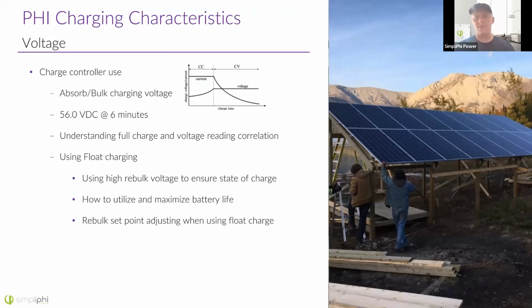Now, another thing you can do if your device does not have an absorb timer is to set the end current. So as soon as the charger drops below, let's say, 2% of the amp hour capacity of your battery bank, you're going to want that charger to turn off. So for example, let's say you've got a 300 amp hour bank. You would want that charger to turn off when 6 amps or less are going into the bank.